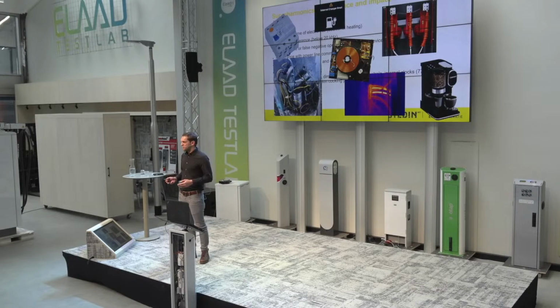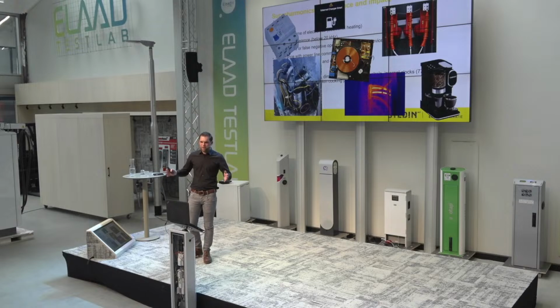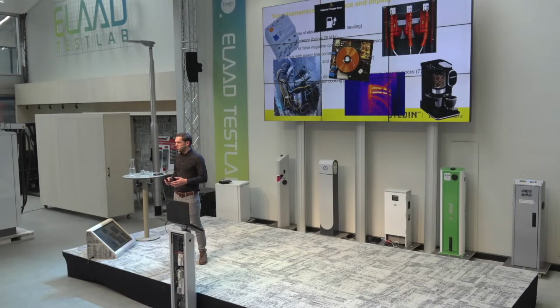Because of this lack of standardization, components or equipment are not really immune to supraharmonics. Things that can occur are, for instance, the failing of protection systems, heating of equipment, failure of it, audible noise from induction cooking plates and other equipment, failing of cable terminations, coffee machines that only make tea. So it's a whole bunch of quite specific problems that occur, mainly due to a lack of standardization.